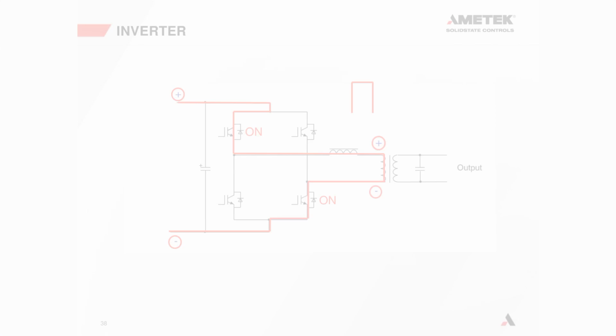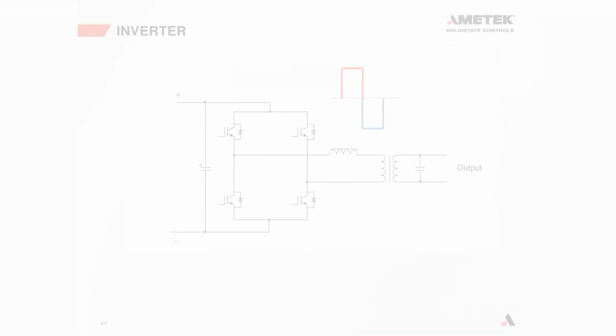Then we switch the other two IGBTs on and these IGBTs off, and it swaps the polarity of the transformer. The positive now goes down through here to this side of the transformer, and the negative goes through this transistor to that part here. That gives us a negative pulse on the input to the primary of the inverter transformer. Put the two together, switching those two IGBTs at 60 hertz, and you'd get a 60 hertz square wave into the primary of the transformer.